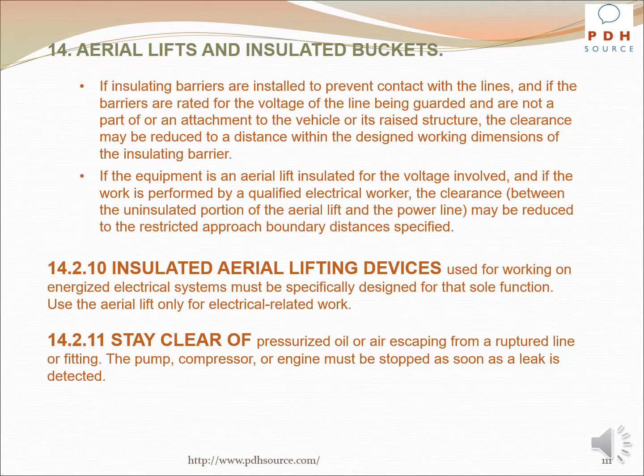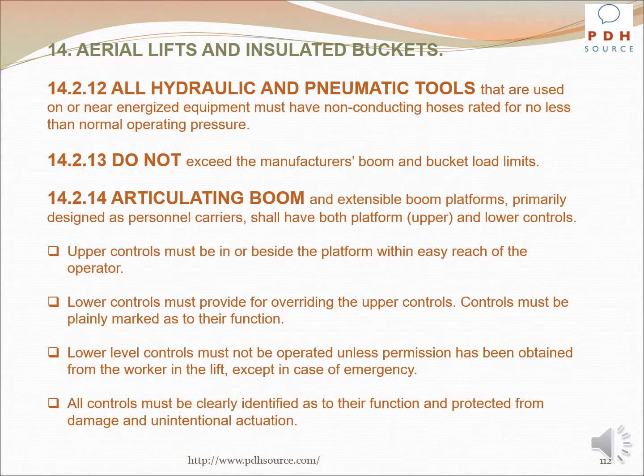Insulated aerial lifting devices used for working on energized electrical systems must be specifically designed for that sole function. Use the aerial lift only for electrical related work. Stay clear of pressurized oil or air escaping from a ruptured line or fitting. The pump, compressor, or engine must be stopped as soon as a break is detected. All hydraulic and pneumatic tools that are used on or near energized equipment must have non-conducting hoses rated for no less than normal operating pressure. Do not exceed the manufacturer's boom and bucket load limits.